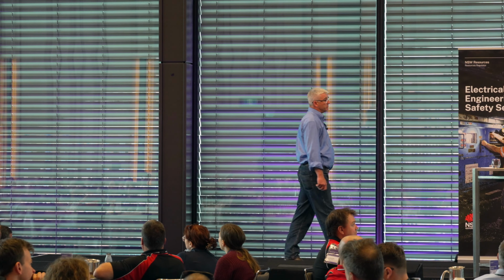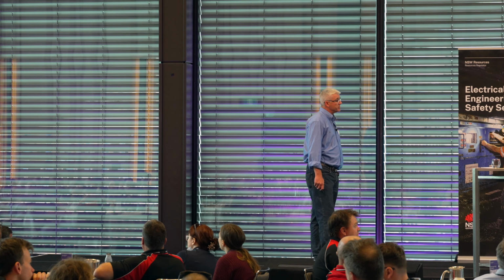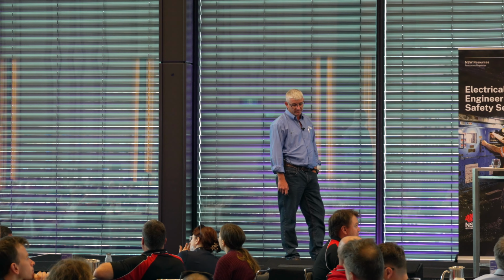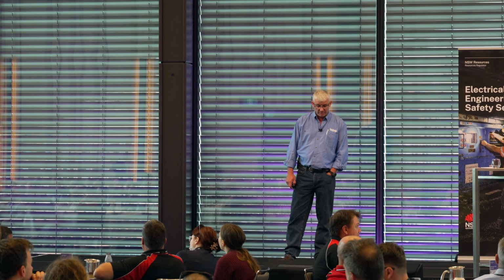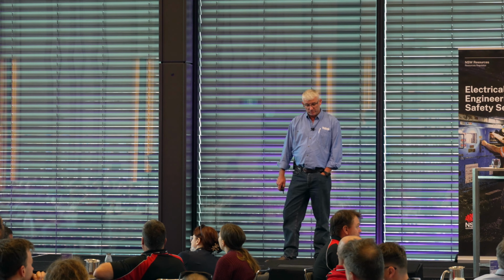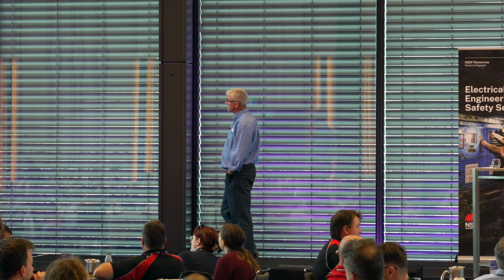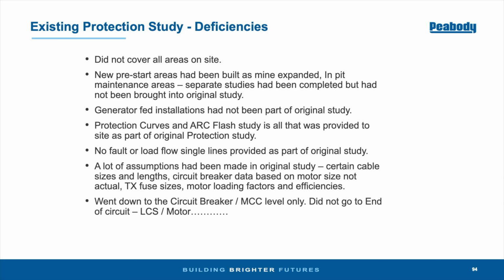The other issue, and you'll see when I get further down to show you what we produce now, is that the protection curves and the arc flash study were all that was provided from that file. There were no fault or load flow single lines provided to site as part of that original study. There'd been a lot of assumptions made on cables, cable lengths, circuit breaker data, transformer fuse sizes, motor loading, efficiencies. At the very start of that document you can see there'd been a lot of assumptions provided when that study had been done.